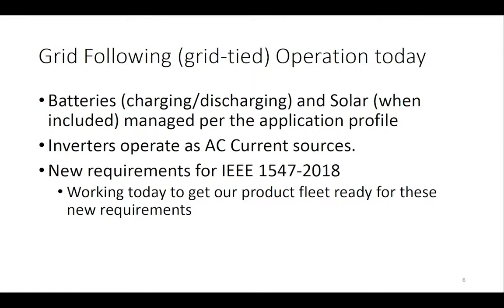And I'm not sure I saw that detailed in any of the background literature for this talk, but hysteretic current control gives you the ability to operate as an AC current source into a grid that's regulated for voltage and frequency. That simple, with full four quadrant operation. Not everyone out there in this industry does that. There's still a lot of people who talk about using DQ control for grid following operation. My opinion is make it a pure AC source.